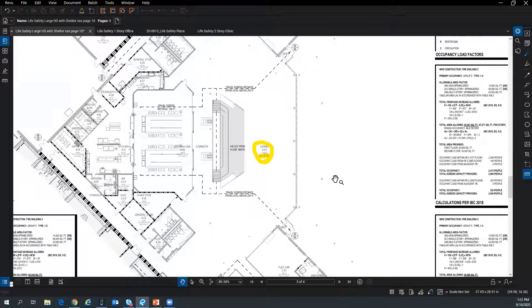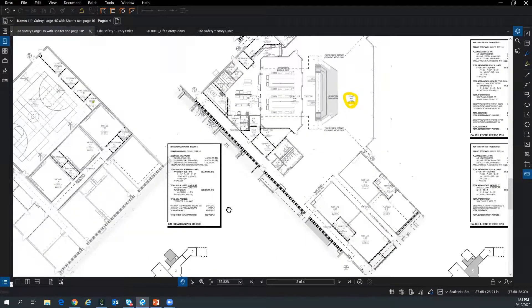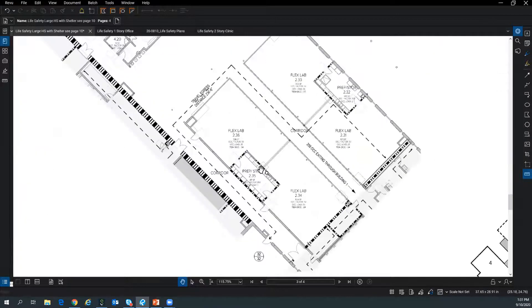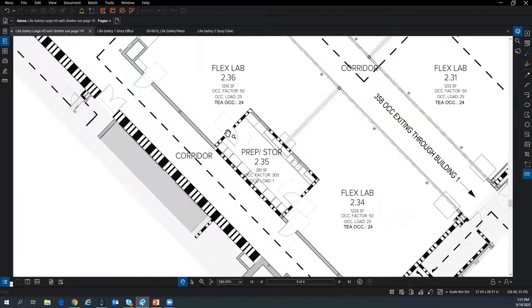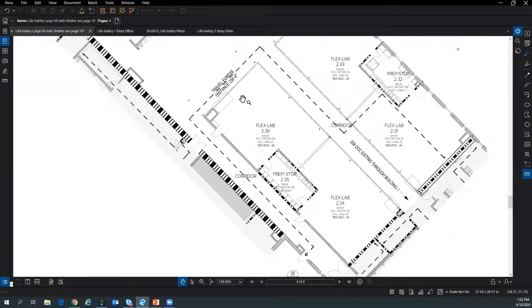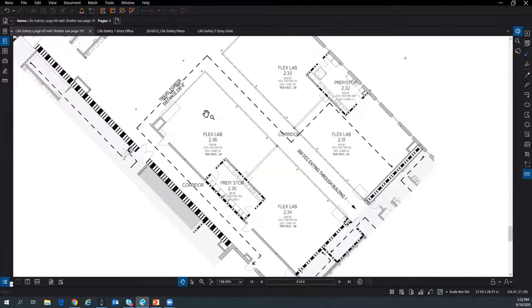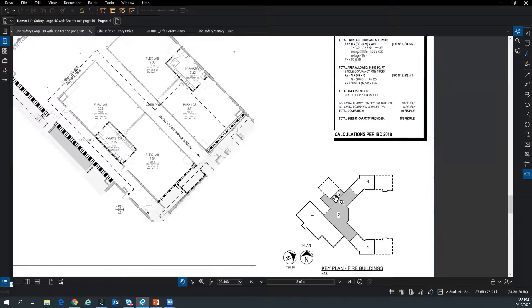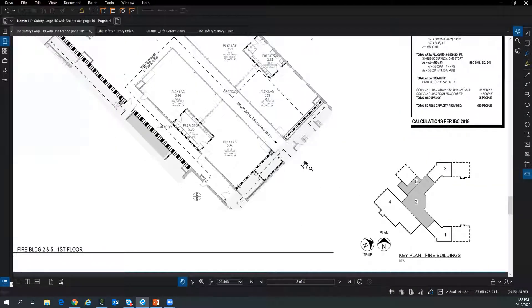You can see the firewalls here. If you remember the symbol — one dot — this is a one-hour protected storage area with very low occupant load, just one person. Most storage rooms are considered unoccupied, but this is fire rated whereas these walls are non-fire rated. Here's another firewall through this area. This is only one section of this very large high school — you would have to check continuity and make sure that the doors in this corridor are fire rated to match.